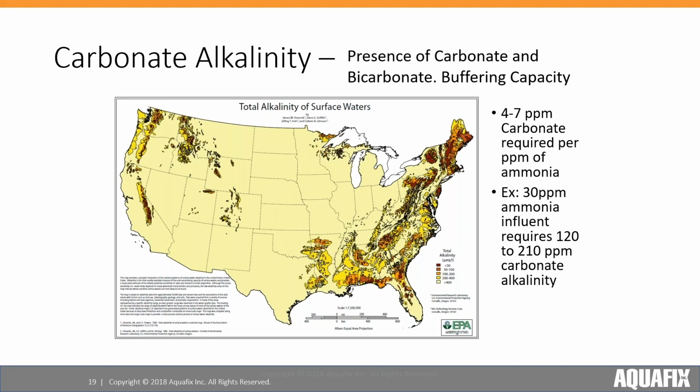If you do run into a case of low alkalinity, some common additives would be soda ash or lime. Lime has a variety of issues, mostly that it's not very soluble, and that makes it pretty difficult to use. When it is solubilized well and used at a high rate, it's also very common to have scaling issues in pumps and lines, and that can cause a lot of operational issues.